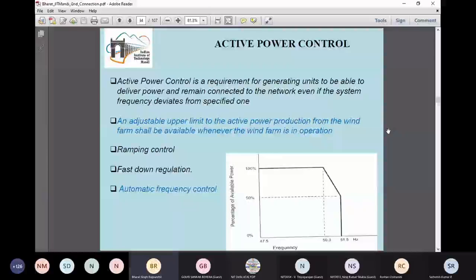And then another one is known as fast down regulation. It means if the grid is in an abnormal condition and is expected to back down the generation from the wind farm, then the regulation expects that the active power from the wind farm can be reduced from 100% to a very low amount. So this is known as fast down regulation. These ranges are generally prescribed in the Indian Electricity Grid Code. Next slide, please.